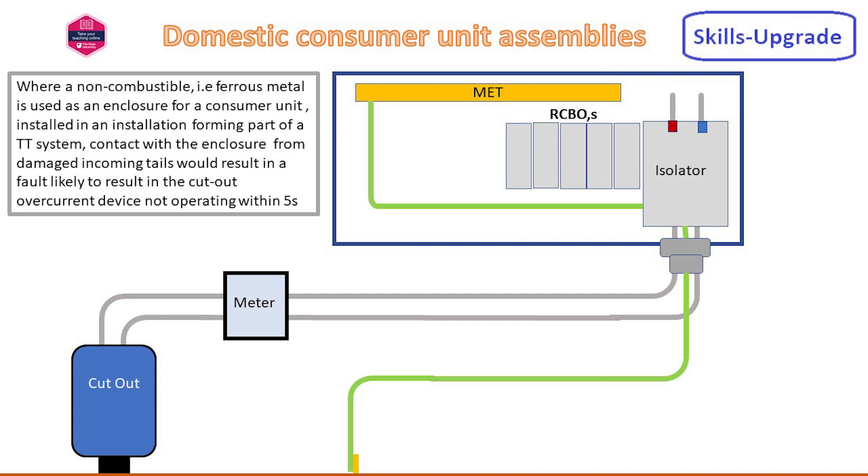With the requirement for non-combustible consumer units to be installed in domestic premises, an issue with TT systems arose. A fault due to the incoming tails coming into contact with the enclosure would result in a disconnection time to clear the fault of over five seconds.